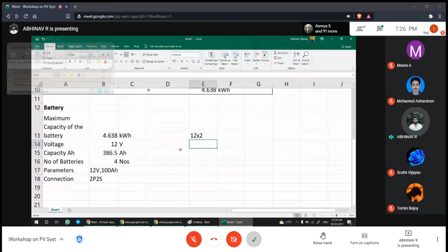So what is the total energy? This is a 24 volt 200 Ah system. See, that is how we design the parameters. So 24 volt into 200 Ah, 4800 watt hour. What we actually require is 12 volt into this much hour. This much was only required, but our battery is slightly oversized to 4,800 watt hours. So you get the point, right? So that's how we design the battery.